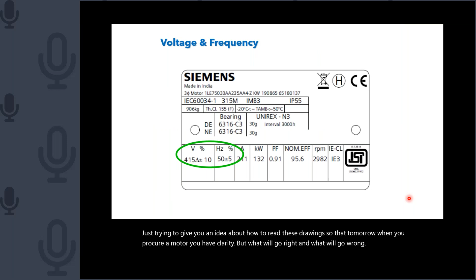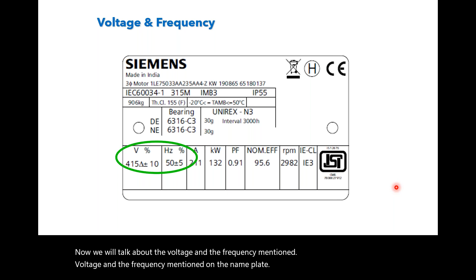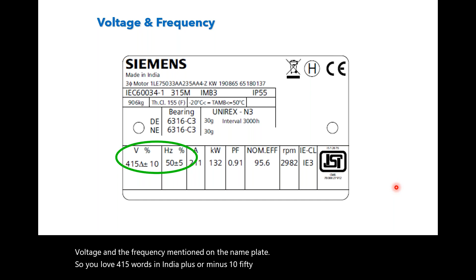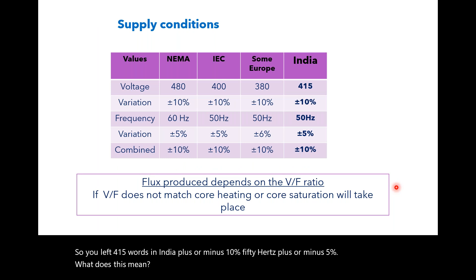Now we will talk about the voltage and the frequency mentioned on the nameplate. So you will have 415 volts in India, plus or minus 10%, 50 hertz plus or minus 5%. What does this mean? Different countries have different supply conditions. Just take a look, only to familiarize you with this. NEMA, North American, like I mentioned, America, Canada, and some South American countries like Argentina, Peru, have 480 volts, 60 hertz. The variations are plus or minus 10%. The combined variation of both voltage and frequency is 10%.